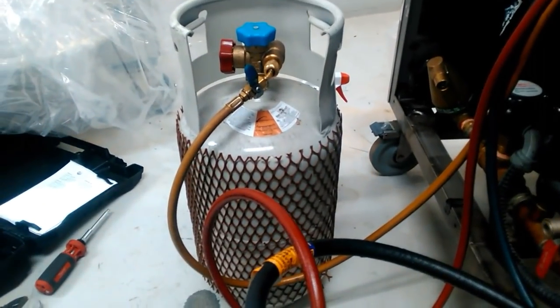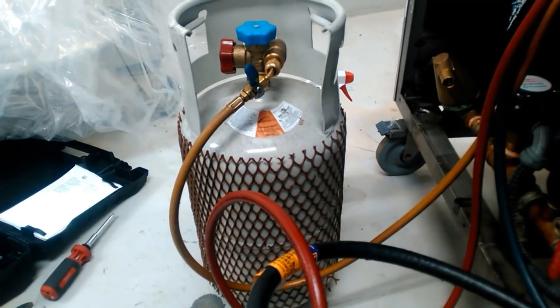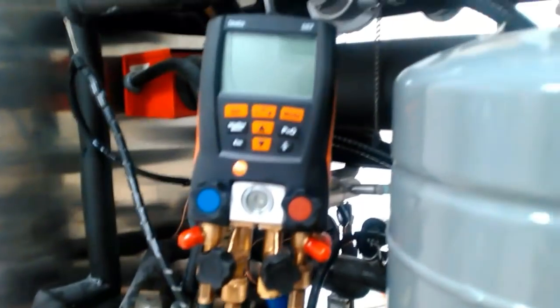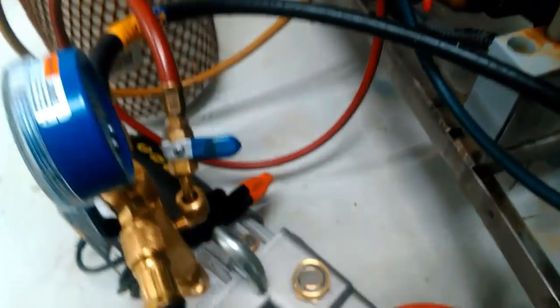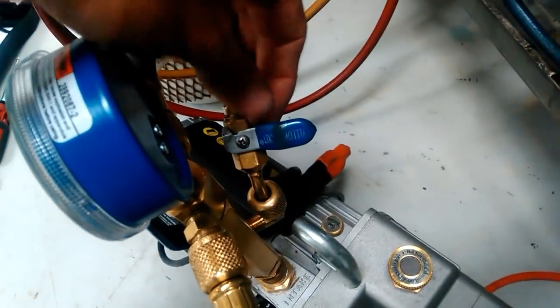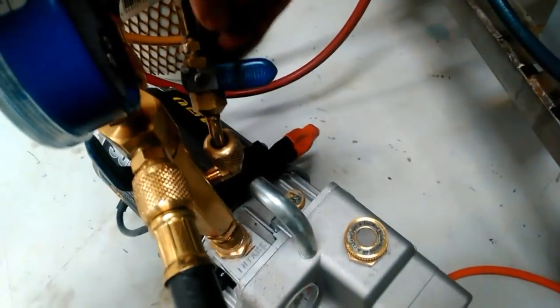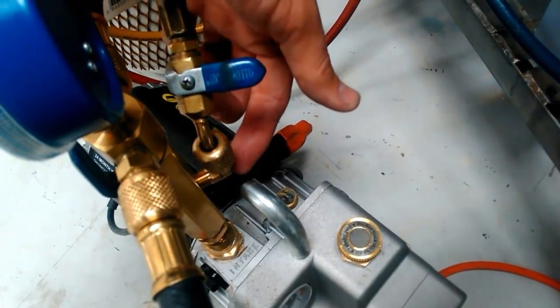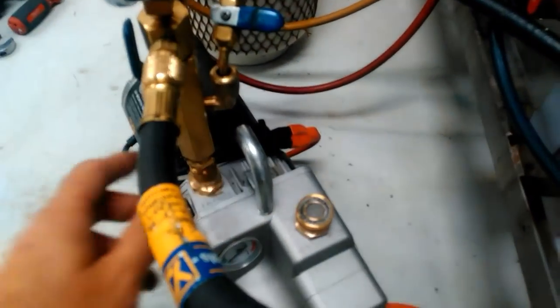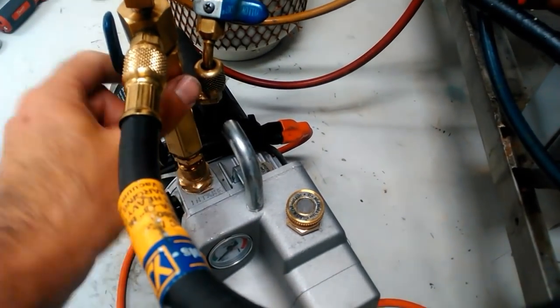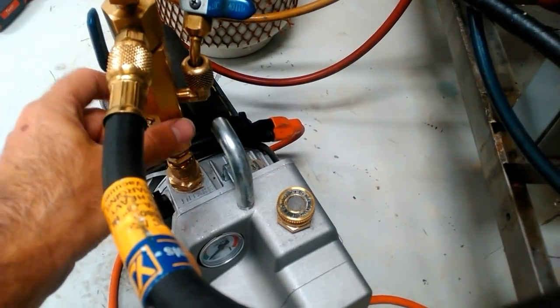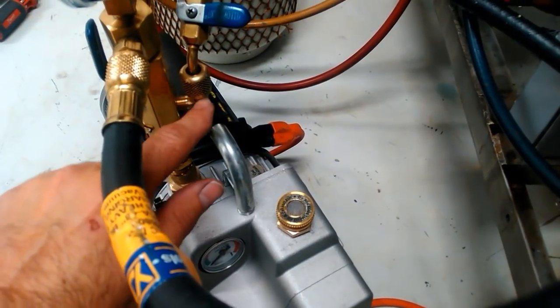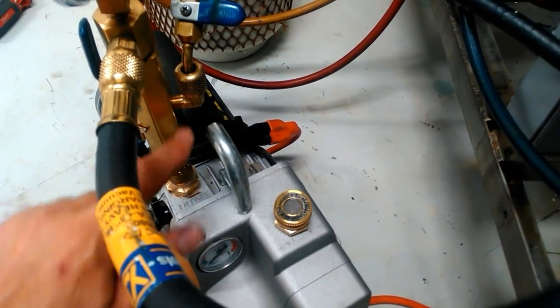We've got our tank cracked open. We've got the gas flowing through. And we have this hose up to this point purged. So up to this ball valve, we have refrigerant. From the ball valve on, we're in a vacuum because that port is connected to the vacuum manifold. So this whole section's in a vacuum, which means this section's in a vacuum.